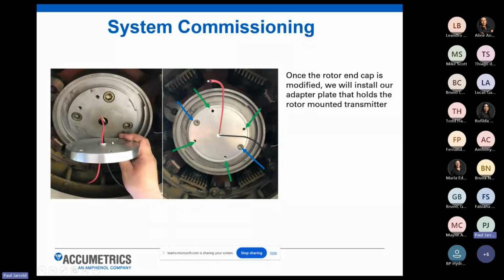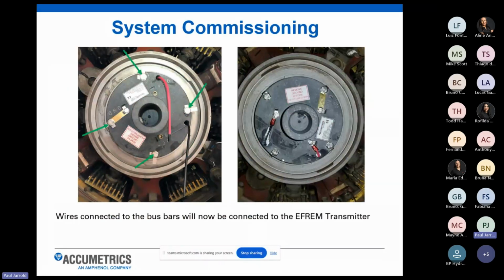We provide this aluminum adapter plate that's designed to pick up the bolt hole pattern on the rotor end cap. So that aluminum adapter plate gets secured directly to the customer's machine, and then we route our wiring into that adapter plate. And now we're ready to install our rotating transmitter. And that's what that looks like.